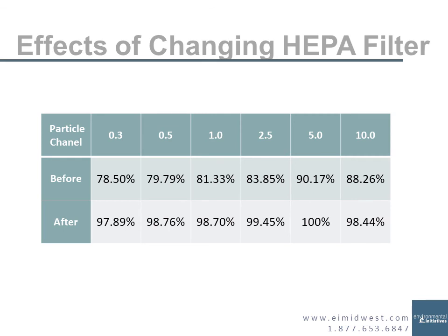What about changing the HEPA filter? What kind of effects does that have? Obviously, this is just one piece of data, but on multiple occasions we did test people's equipment before and after they changed their filters. And sure enough, as you could guess, when you change your filters, you get better filter efficiency.